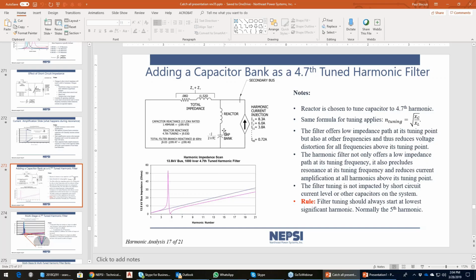Okay, so with capacitor banks, you're going to push your resonance down to a lower frequency. If you have harmonic filters, you're going to push more current into your filter bank as a result. And I think it's fair to say that you're increasing the overall impedance of the network, so you will have a corresponding bump in voltage distortion within the plant for that same system.